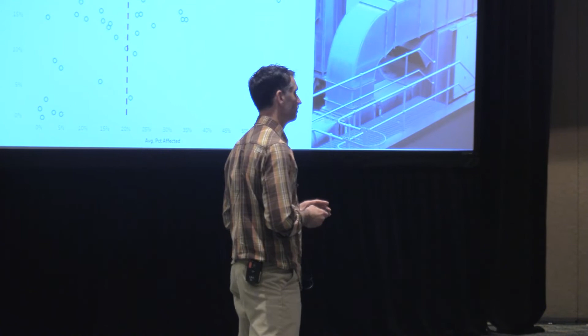Yeah, when you look at a lot of data, it's our platform, I can't really speak to that. I would say relative humidity too much, but I don't typically see supply temperature sensors failing that much. But we see discharge air temperature, supply air temperature reset strategies fail constantly. Those are all the problems. We understand we see those related to temperature reset sequences failing, we see those failing quite a bit too. So I see a lot of alignment with your upper right pile there. Yeah.